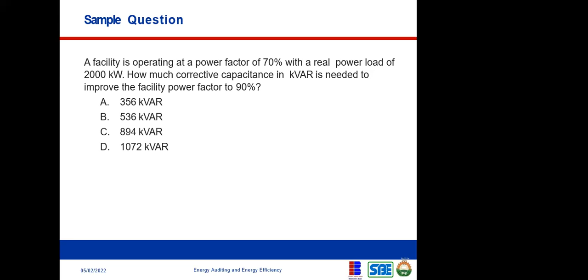We take this 0.536 and multiply it by 2,000, our real power. So kVAR capacitance equals real power in kilowatts times the table factor. At 90%, the table factor is 0.536, so 0.536 multiplied by 2,000 gives you your kVAR, which is 1,072 kVAR. So the answer is D in our question.